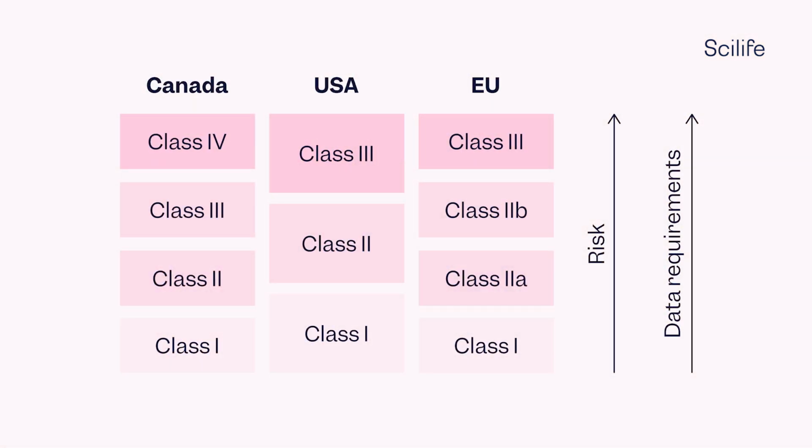Not all devices require design control. Devices that are Class 2 and Class 3, along with certain Class 1 devices, require design control in order to fulfill their regulatory requirement. Class 1 devices like crutches and bandages do not need design control as they are low risk.